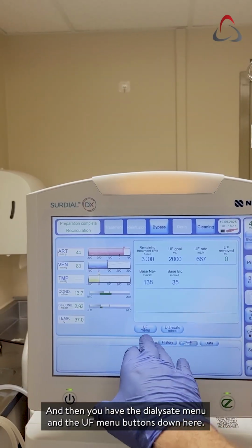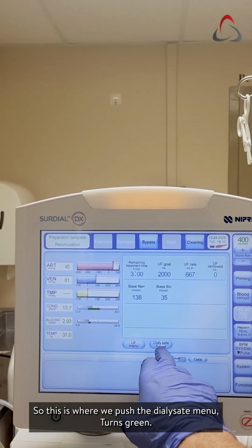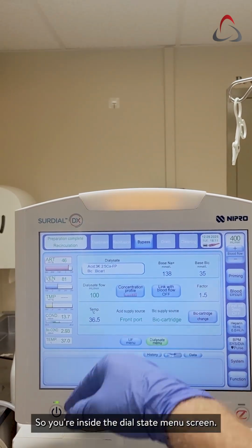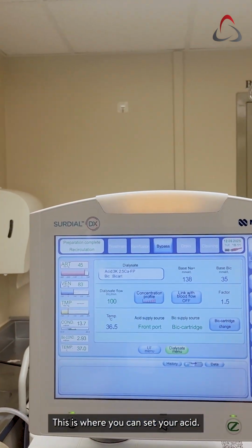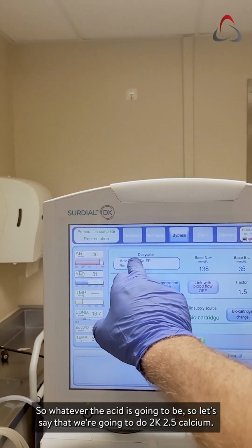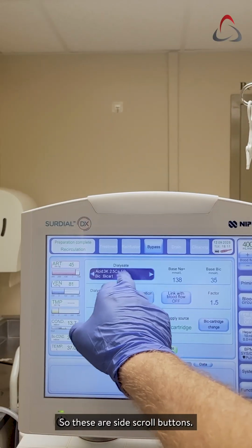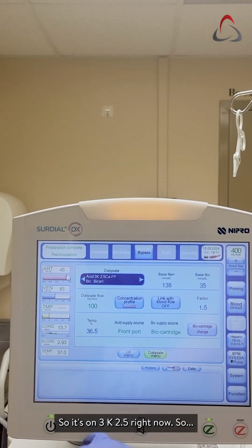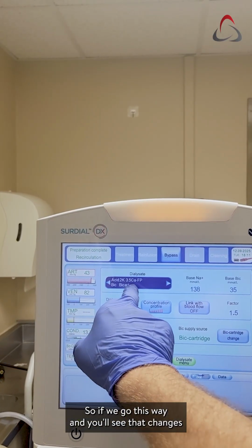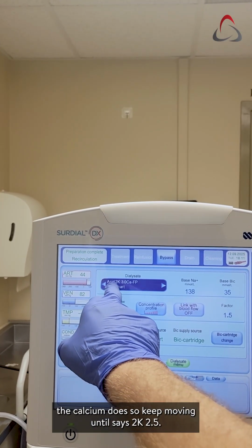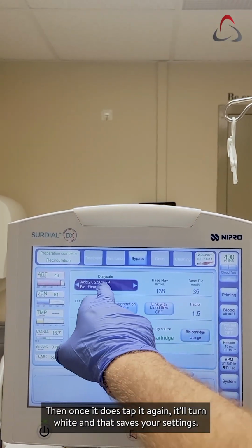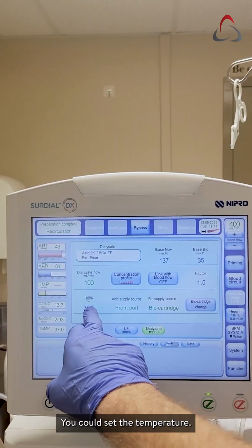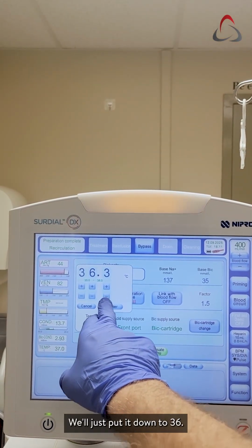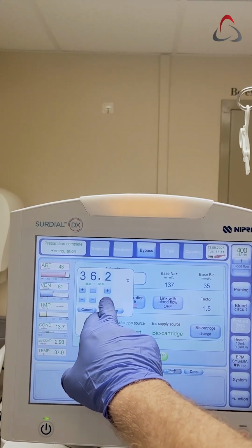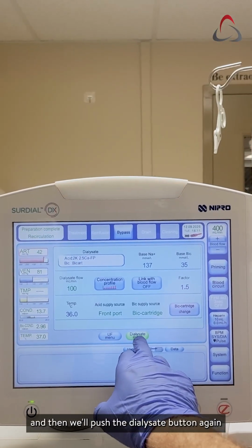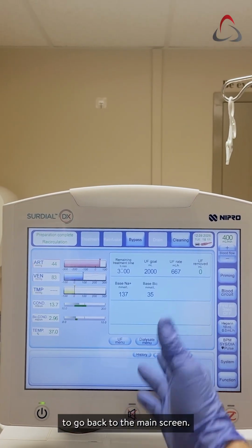And then you have the dialysate menu and the UF menu buttons down here. So this is where if we push the dialysate menu, it turns green, so you're inside the dialysate menu screen. This is where you can set your acid, so whatever the acid is going to be. So let's say that we're going to do 2K 2.5 calcium. So these are side scroll buttons, so it's on 3K 2.5 right now. So if we go this way, you'll see that the calcium changes. So keep moving until it says 2K 2.5. Then once it does, tap it again and it'll turn white, and that saves your settings. You could set the temperature. We'll just put it down to 36. Push enter. And then we'll push the dialysate button again to go back to the main screen.